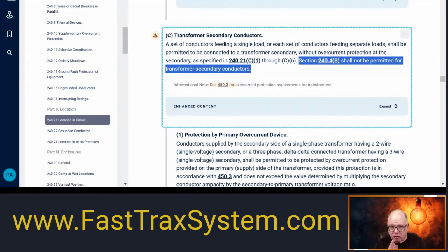We're like, okay, since those conductors were 380 amperes, can I terminate them on a 400 amp overcurrent device? Not under the tap rules, and certainly not under the secondary rules. I can't. So I'd have to increase the size of my conductor. In this case, in order to make sure it's at least the rating of the overcurrent device, I would increase this from a 500 kcmil up to a 600 kcmil, which is going to have adequate ampacity to be equal to or greater than the rating of the overcurrent protective device. Okay, that type of scenario. All right, so that's an important part to realize on those tap rules.